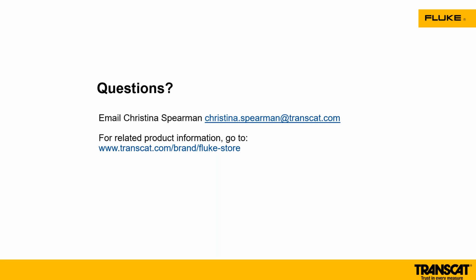Okay, and the next one, do Fluke multimeters default to reading RMS? Yes, most Fluke meters, and you will see that it will say true RMS, will default to that as soon as you turn them on. That will be true RMS. Now, there is an average responding aspect to most of our meters. There's a little bar scale in the LCD screen that you can look at. 90% of Fluke's DMMs and clamp meters will be true RMS meters. There are a select couple that are average responding, but not too many people use those anymore out in the environment. Only really our military still uses the average responding type of meter.